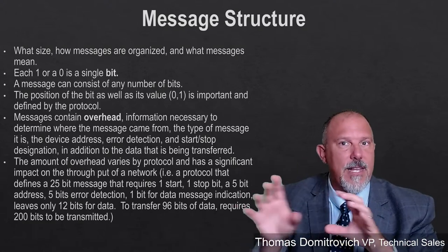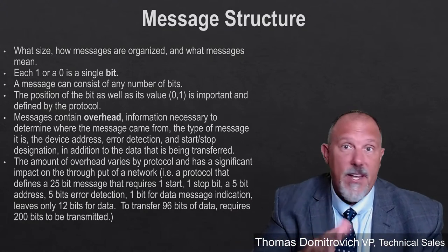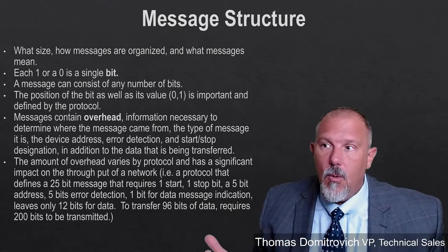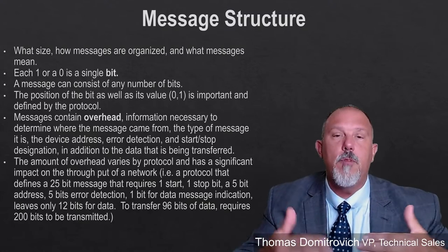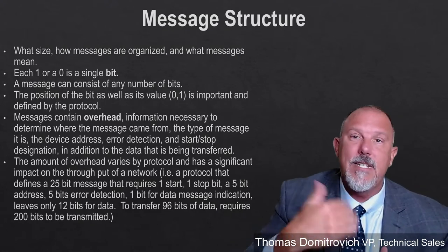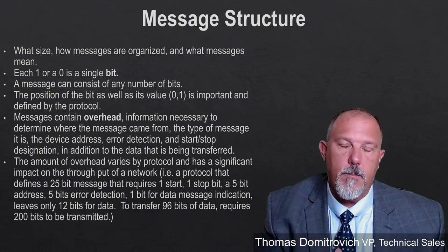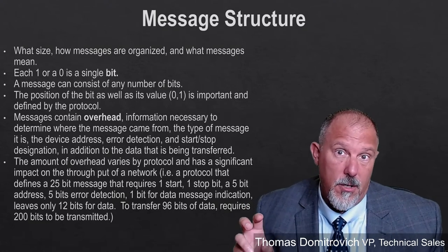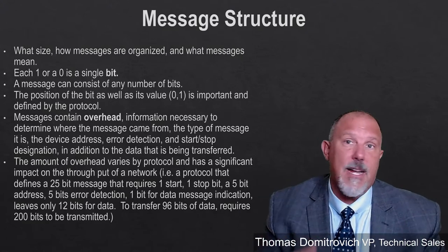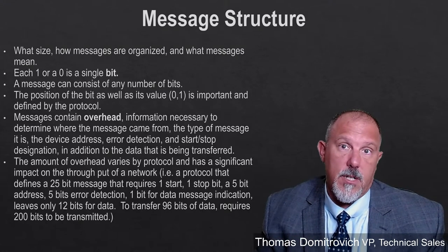And you can't intermix. That's why we have industry standards like Modbus and Modbus TCP, and you've got to be careful there, because some people will throw in their own little variations. Why would I throw a variation into Modbus? Well, maybe my device does so much more than what a standard Modbus device does. I have more data than Modbus permits me, so I need to come up with some method to leverage the existing protocol, but then do something a little special to be able to give you more data for my special functions. Like, I might be able to give you waveform data, and it might come back over a series of data streams, of data packets.